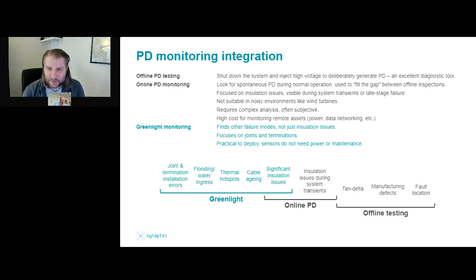Obviously, this has some issues with the logistics required to actually install the equipment, because unlike Synaptec's approach, these sensors need local power supply, they need some kind of data network, some approach to time synchronize things, most likely. So it becomes impractical to deploy this at scale. Typically it's done in a sparse way with relatively few installation locations, or it's done on a temporary basis, like a handheld instrument that people would take during periodic maintenance campaigns.